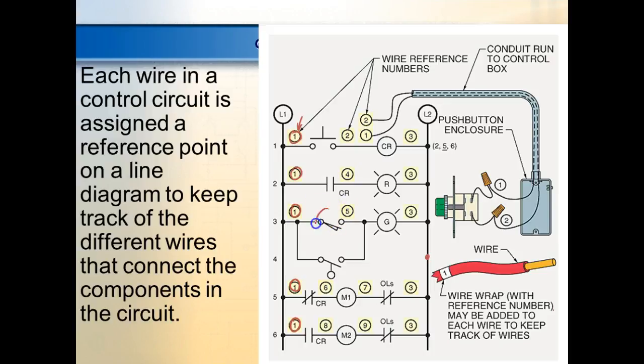As soon as I go through a device, it changes numbers. Now why don't we have a number down here? It's electrically the same as that. So if I wanted to measure across this contact right here, I can find 1 to 5, and 1 to 5 is across that contact no matter where it's at. Everything that's connected together gets the same number. Every time you go through something, it gets another number.